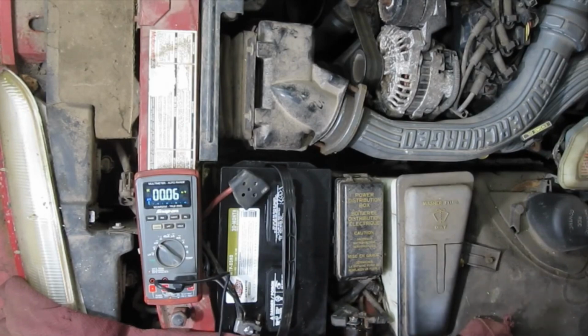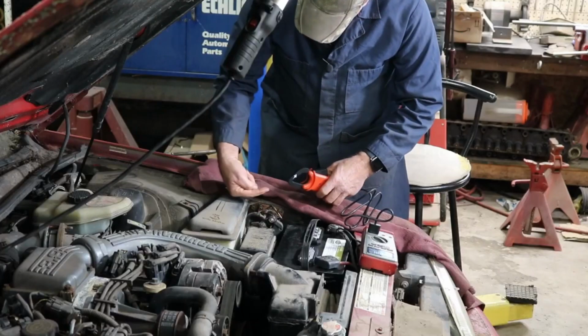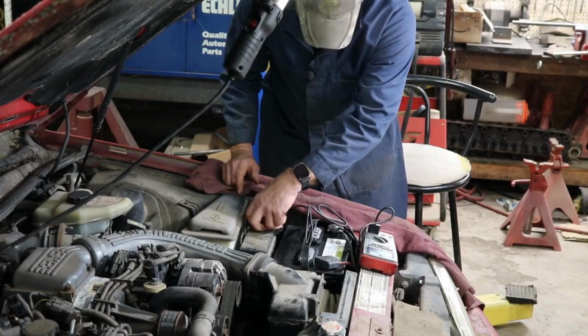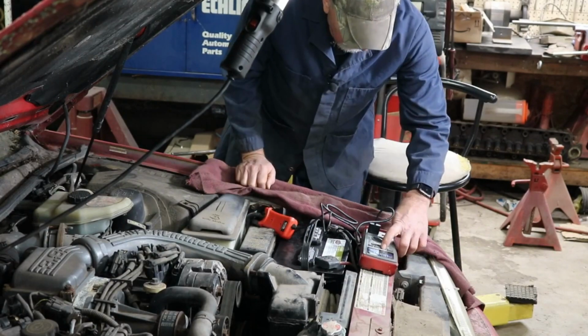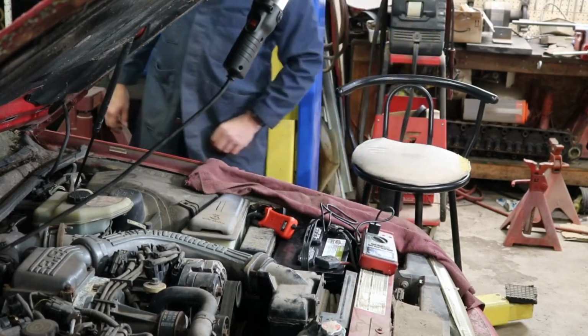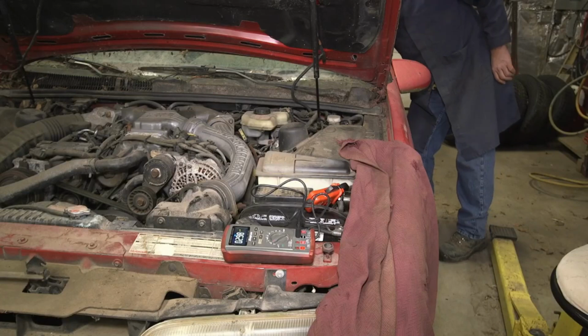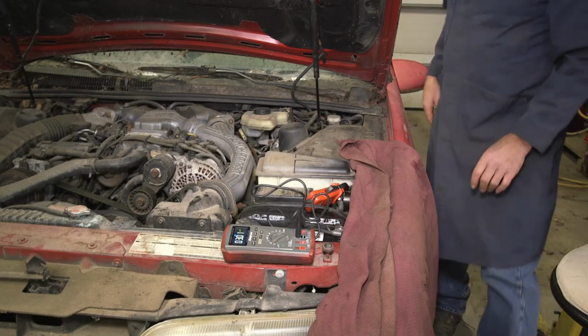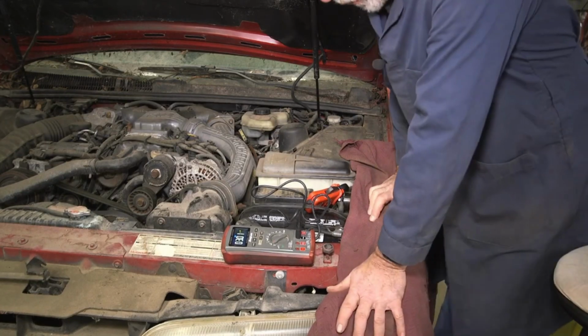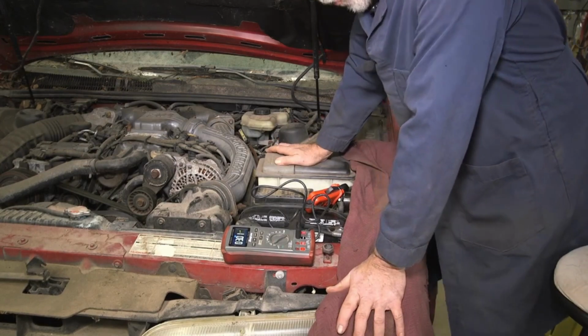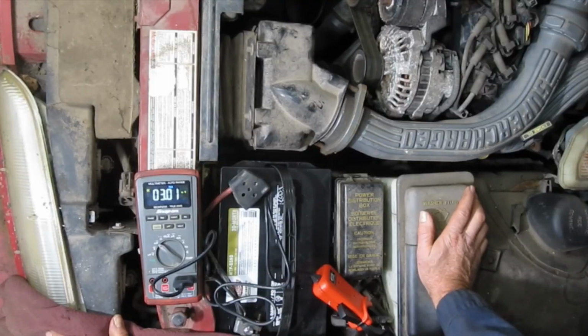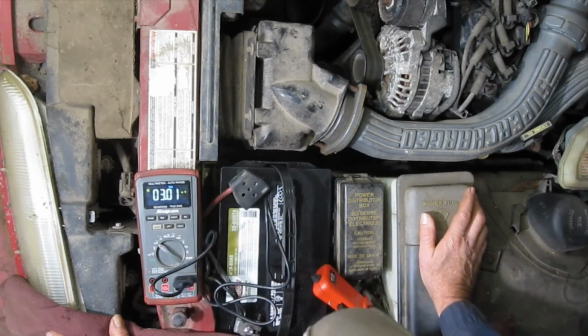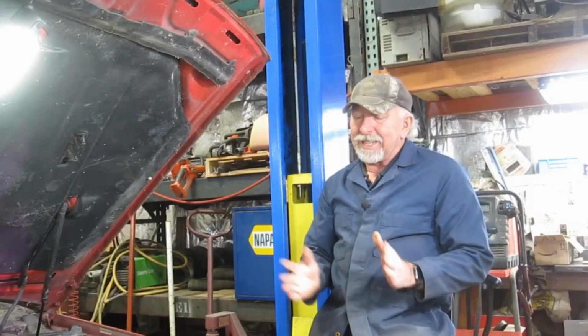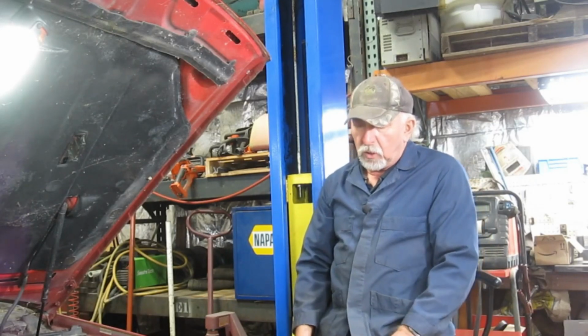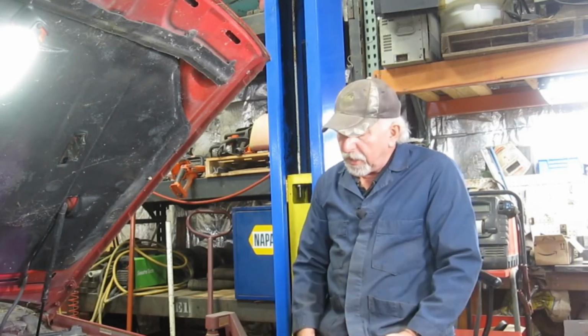The current flow is going to come into the wire in that direction, so I'll put the amp probe on there and do our test. Okay, looks like we have around 3 amps of current draw coming into the solenoid. That's on the lighter end of the current flow, but within the acceptable range.